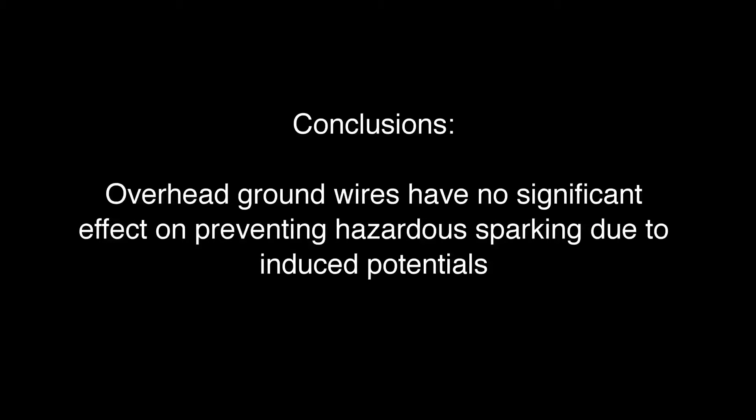Although overhead ground wires may act as effective lightning interceptors, they have no significant effect on preventing hazardous sparking due to induced potentials. It should be noted that, since overhead ground wires which are meant to intercept lightning strikes must be taller than the tanks they are protecting, they could attract more lightning strikes to the site and increase the tank's exposure to the effects of electromagnetic waves.